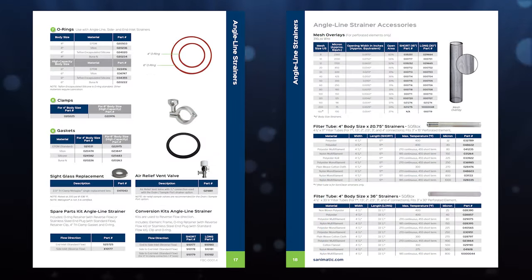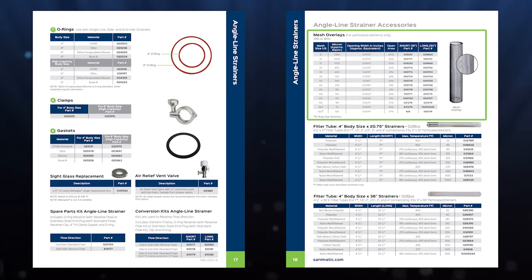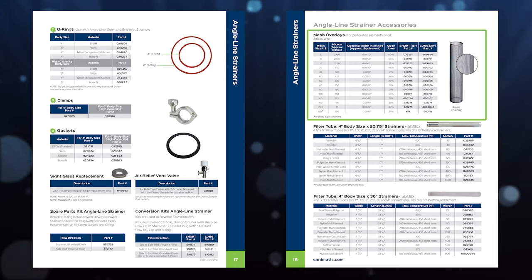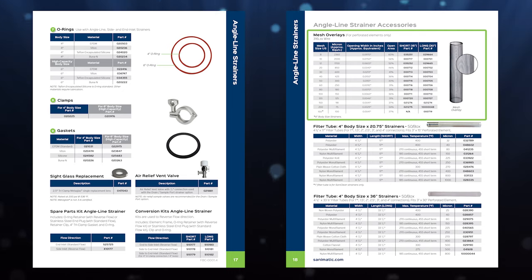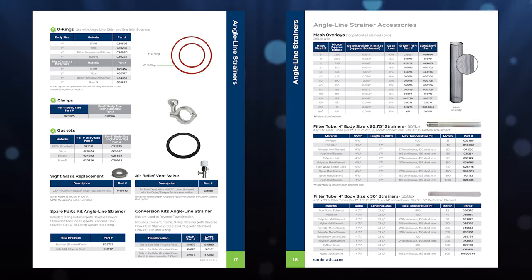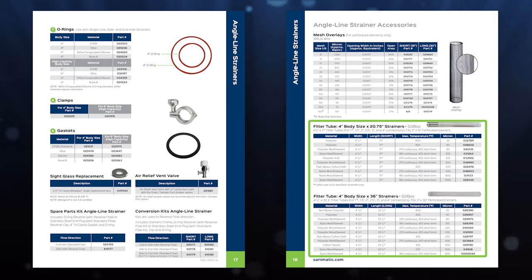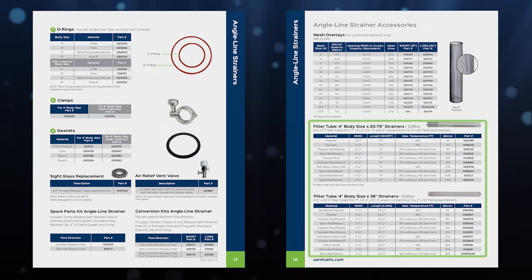If you're using a perforated element and looking for mesh overlay or filter tube information, under the accessory section of the applicable strainer section we also have information on that. For mesh overlays, sizing is based off of mesh size US, but that also comes in microns or opening width in inches. You can find the equivalent mesh size that we have. Open area percentage information is also in this table. If you're using a filter tube with a perforated element, the specification size we use is micron. Under the filter tube section, you can see the different micron ratings and the materials and max temperatures associated with those particular filter tubes.